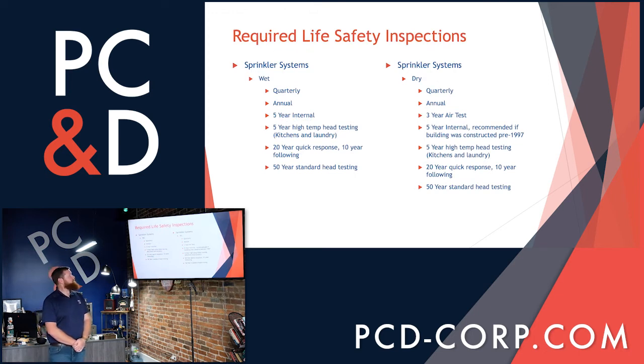With that being said, we'll jump right on into your sprinkler systems. Typically you have two types, your wet and your dry system. The distinguishing factor, of course, is that the wet system is indeed wet. Your sprinkler lines are filled with water continuously and pressurized either by a pump or by natural gravity. The other is your dry system, which has compressed air inside your sprinkler system above the riser and controlled by a flapper valve. So if a sprinkler head were to pop, the pressure is released and therefore water will flow.